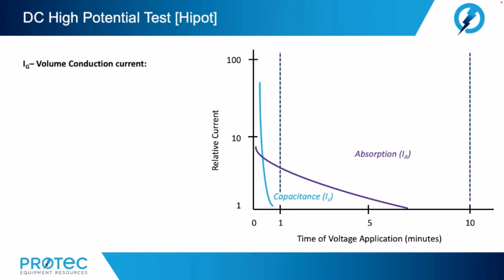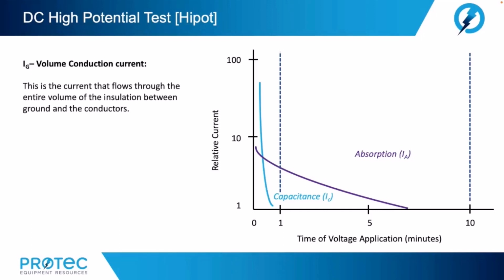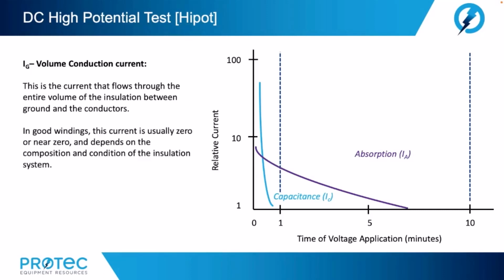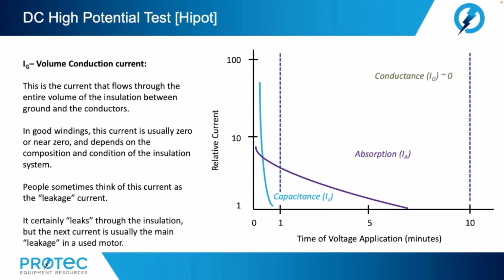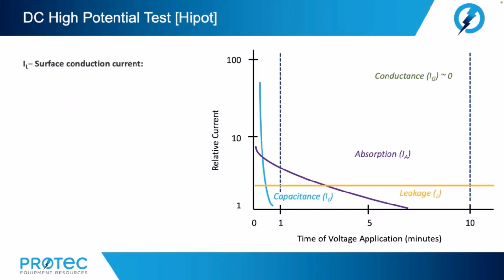We also have that volume conduction current. This is the current that flows through the entire volume of the insulation between ground and the conductors. Now again, in good windings, this current is usually zero or near zero and depends on the composition and condition of the insulation system. People sometimes think of this current as the leakage current. It certainly leaks through the insulation, but the next current is usually the main leakage in the used motor.